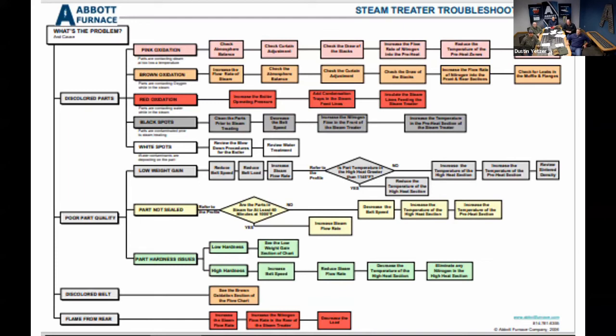We see brown oxidation, and brown and red sometimes are a little close together because they're that red rust kind of brown color. But the more brown color is typically where the parts are seeing oxygen while they're at elevated temperature. A more red oxidation or spots of red is typically where they're contacting water while they're in steam.